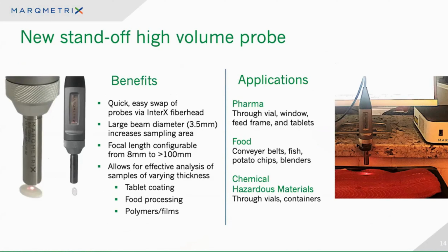We also have our newest probe, our new standoff high volume probe. Some of the benefits of this probe are that it's adjustable. We can adjust the focal length on purchase between 8 millimeters and 100 millimeters of standoff. It provides a large beam diameter, which increases our sampling area. And if you do a lot of work with heterogeneous samples, you get an averaging effect with a larger spot size. It allows for effective analysis of samples of varying thickness. Some of the applications we're using them on now are tablet coating, food processing, polymer films, control and process control and understanding.